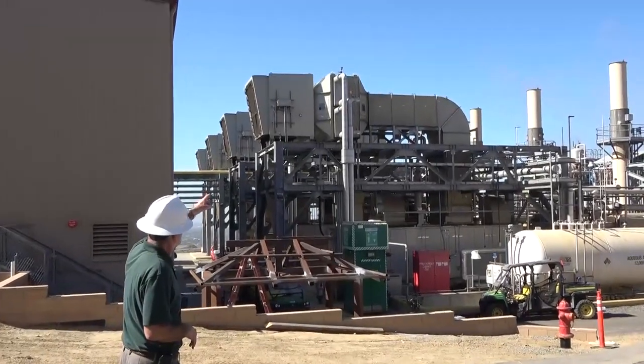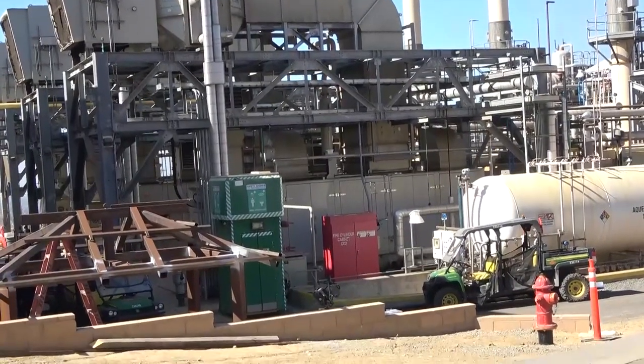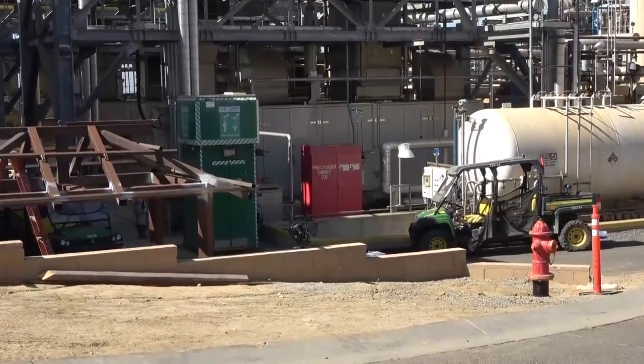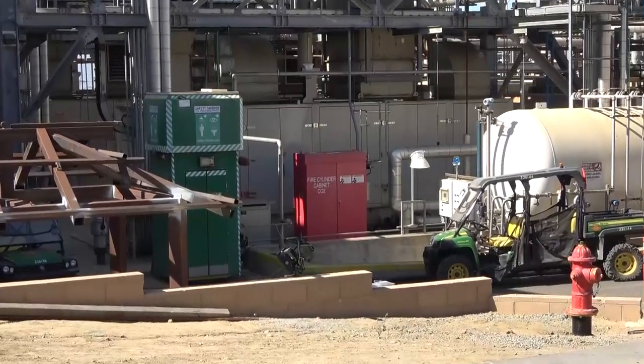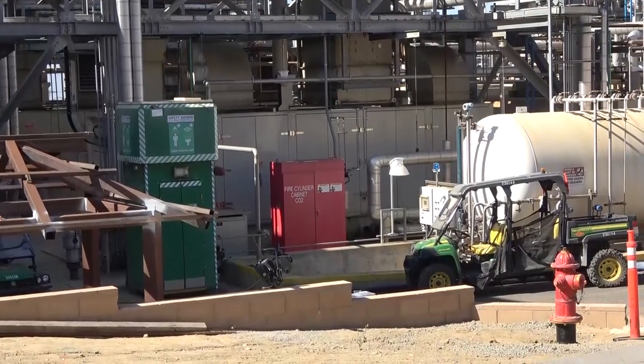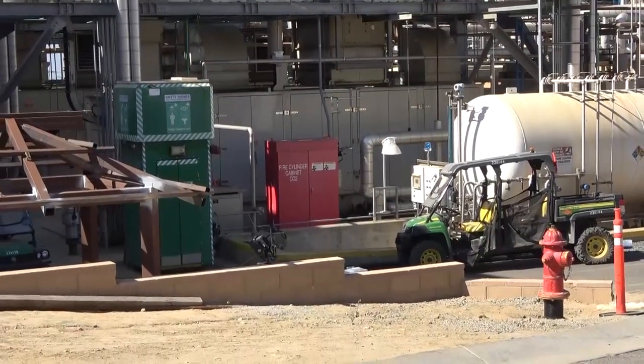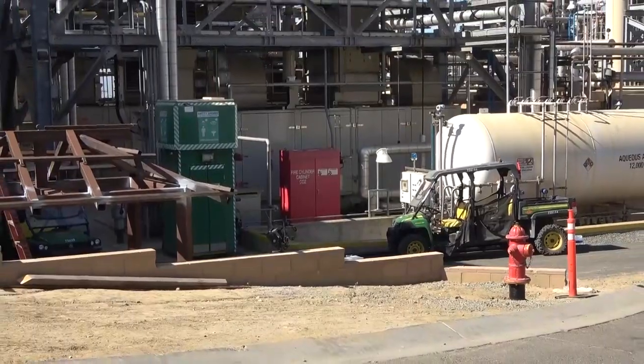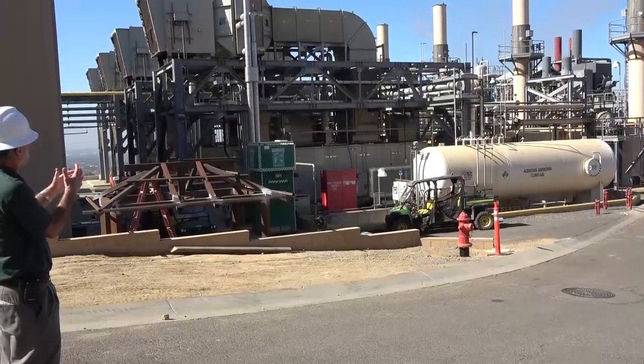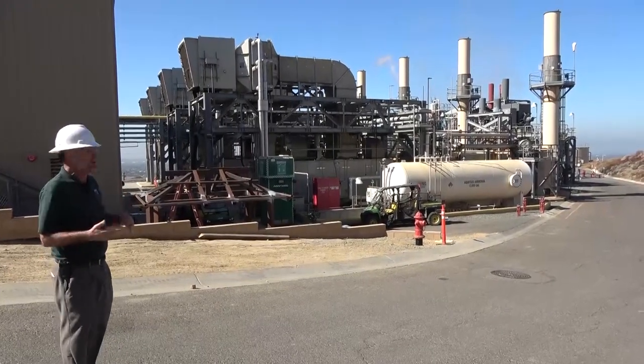The pre-chilled air goes into the top of the gas turbine, which is running right now and enclosed in a large soundproof container resembling a shipping container. That container holds the compressor, combustion chamber, the gas turbine itself, and the generator. This is a cold end generator — the electric generators are on the far left, combustion occurs in the middle, and the discharge exhaust goes into the heat recovery steam generator.